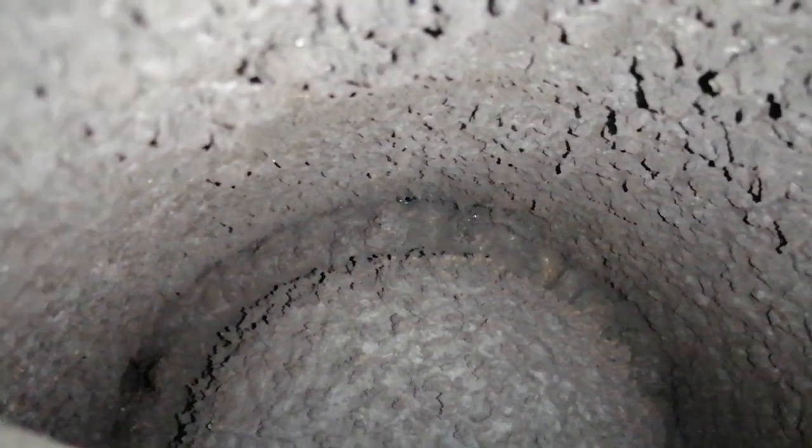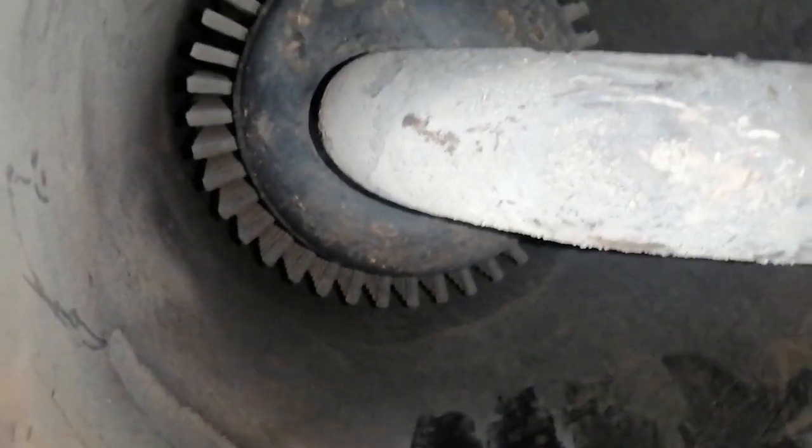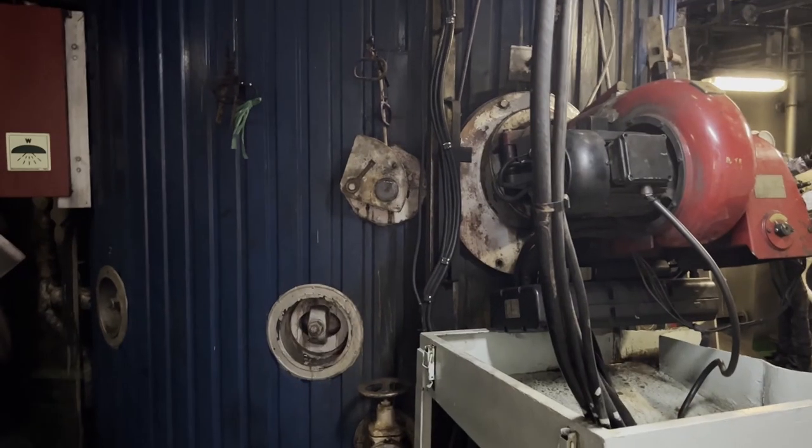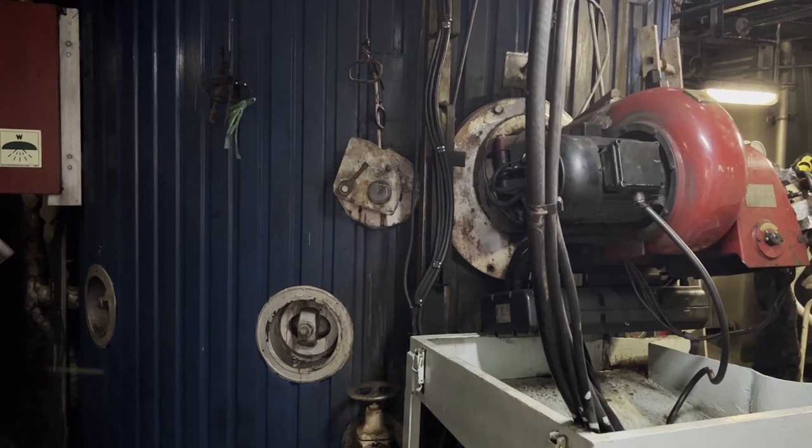This is one of the reasons for backfire. You can see there is no place for exhaust gas which has been burnt to go out towards the manifold. It is totally stuck, full of carbons. Not only the fuel which is not burnt and deposited inside the furnace area will cause backfire, this kind of environment will also cause a backfire.